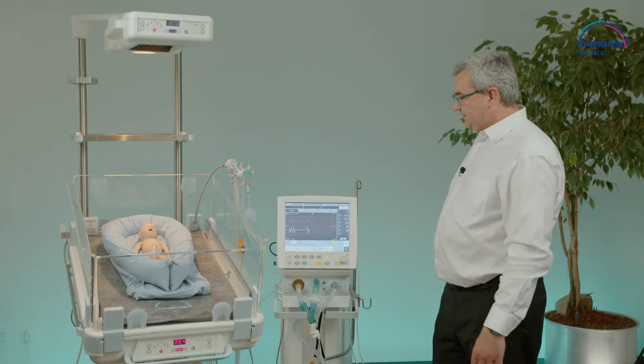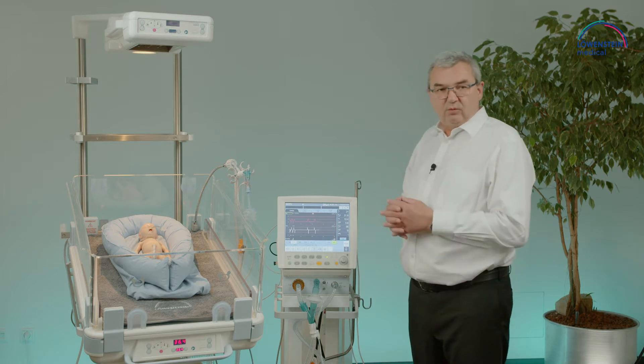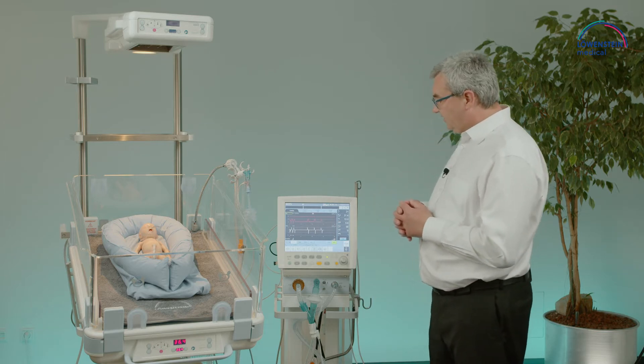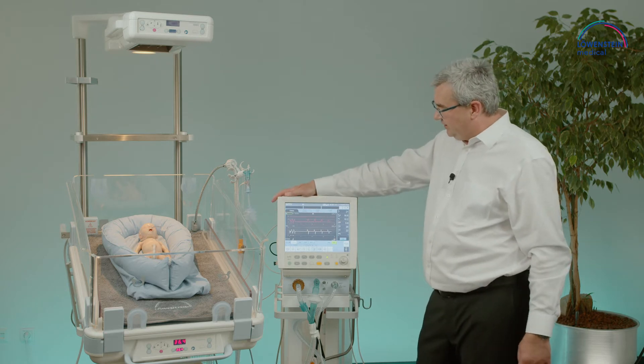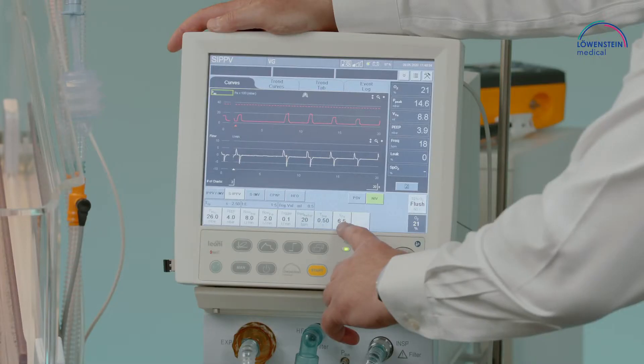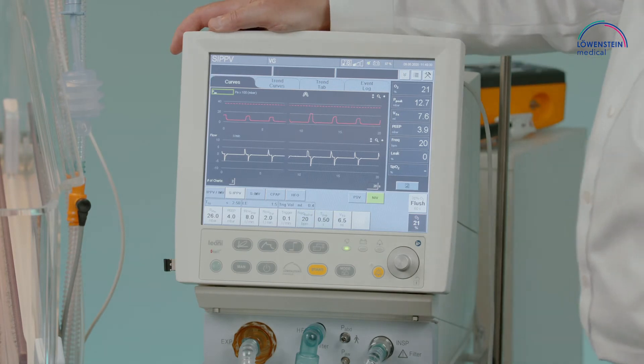On Leoni Plus we have several ventilation modes which have a tidal volume guarantee inside. I will start with the actual mode SIPPV, where we have adjusted a tidal volume guarantee to 6.5 milliliters expiratory tidal volume.